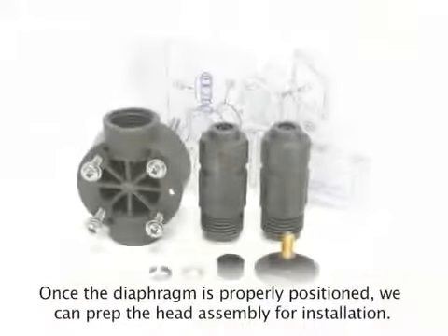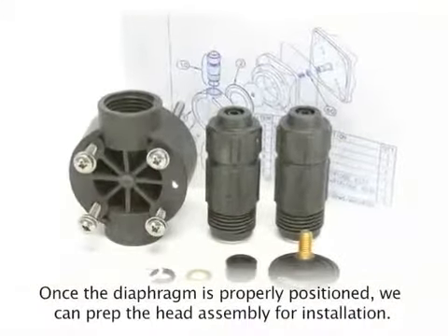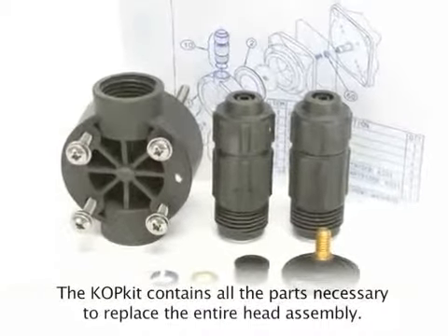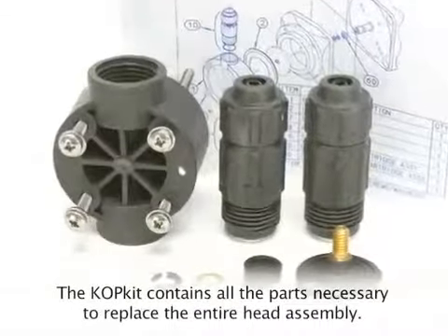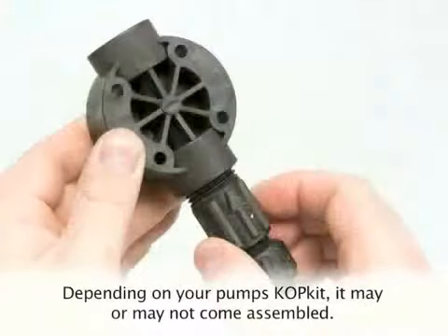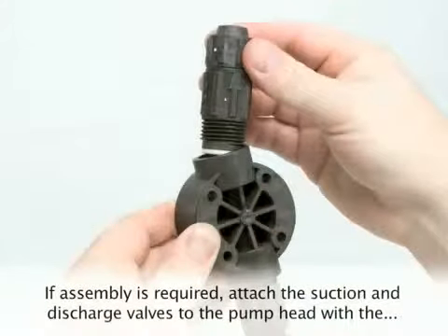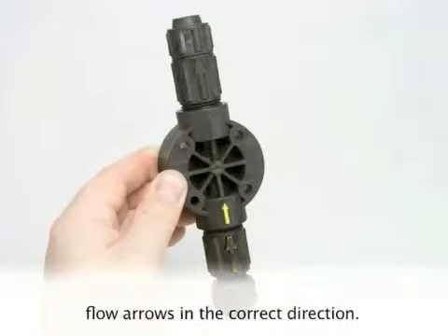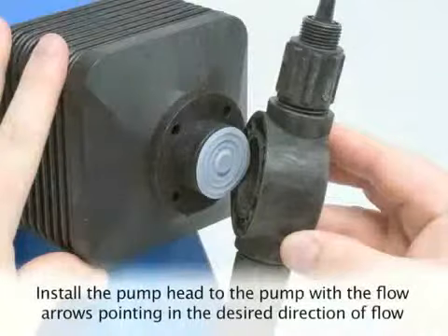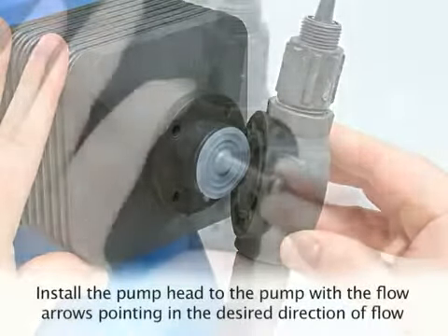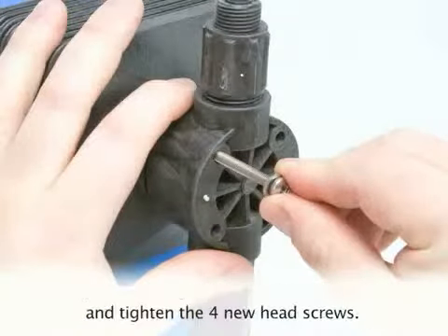Once the diaphragm is properly positioned, we can prep the head assembly for installation. The KOPkit contains all of the parts necessary to replace the entire head assembly. Depending on your pump's KOPkit, it may or may not come assembled. If assembly is required, attach the suction and discharge valves to the pump head with the flow arrows in the correct direction. Install the pump head to the pump with the flow arrows pointing in the direction of flow, and tighten the 4 new head screws.